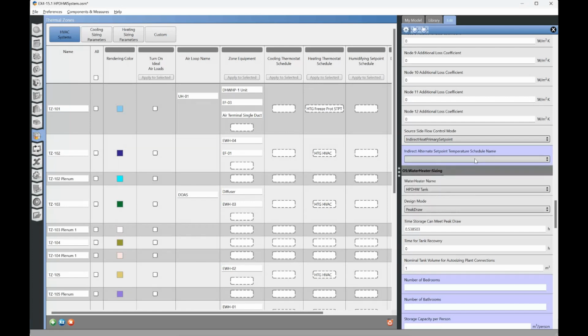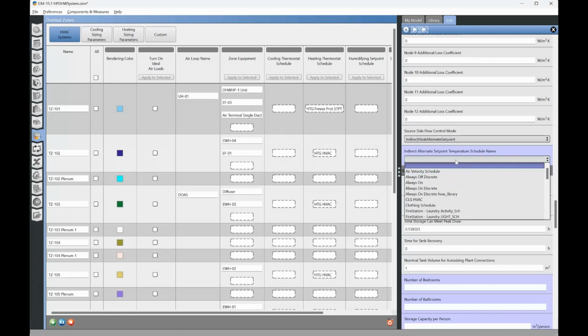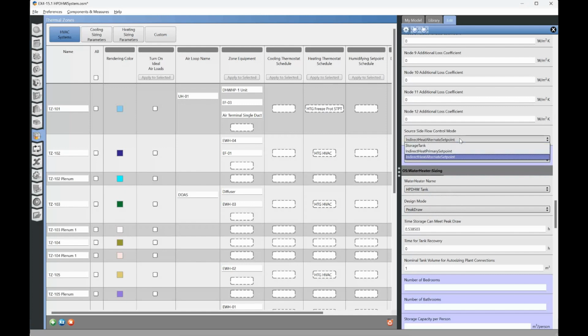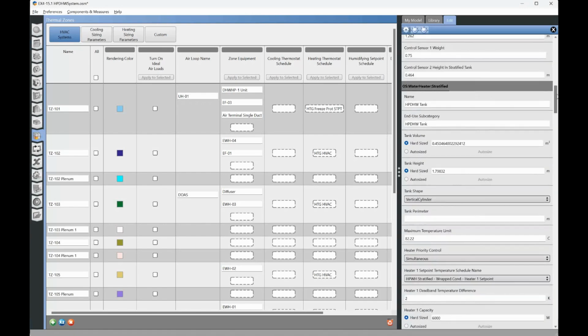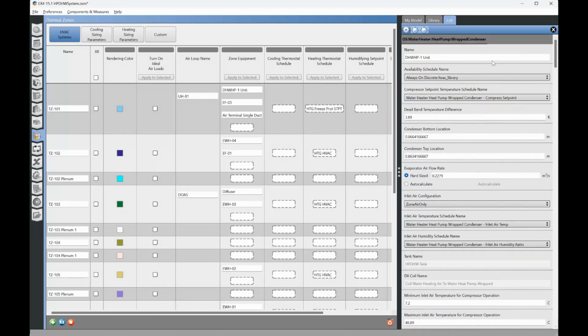And then this is the schedule that's associated with that. So if you are using the alternate set point, you can assign that schedule here for that compressor. But right now we're just doing the primary set point, so the compressor is attempting to meet that temperature set point, which is specified all the way up here. This is the compressor set point, and this is the dead band. So once the tank temperature drops below this set point by 3.89 degrees, then it sends a call to the compressor to start operating.